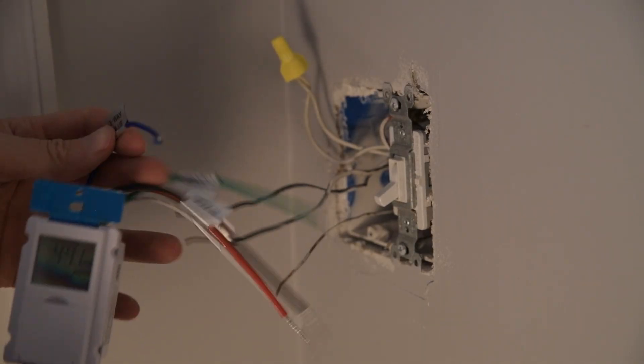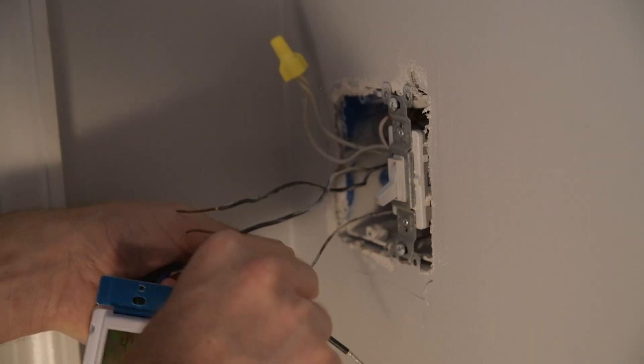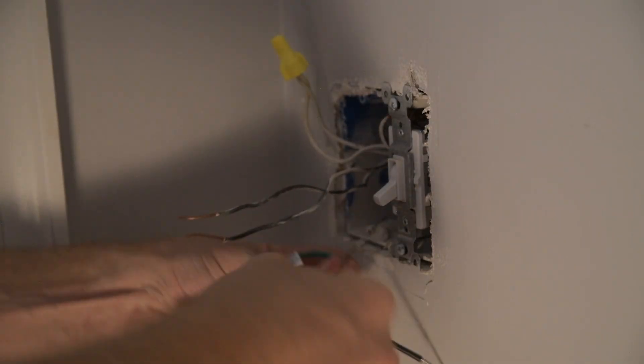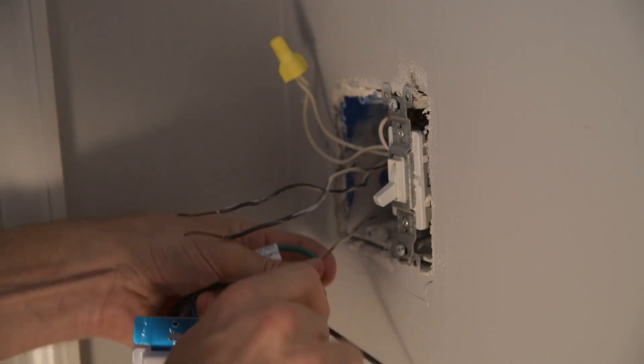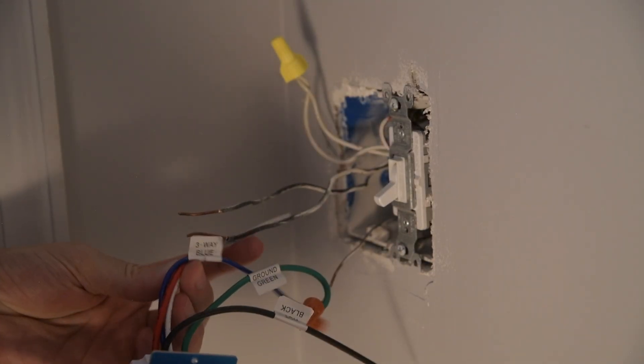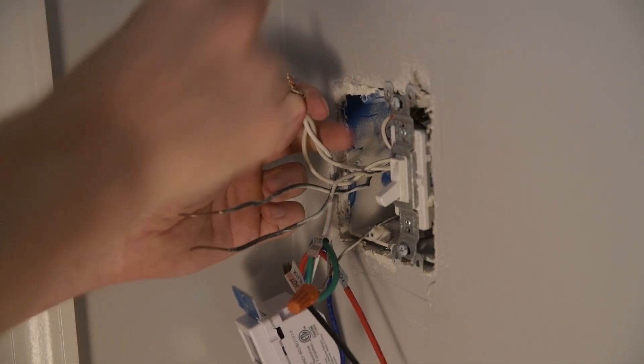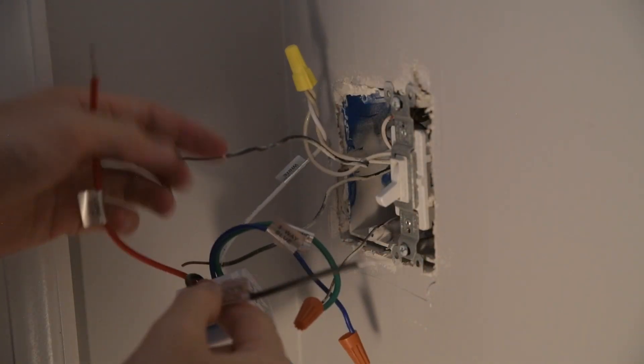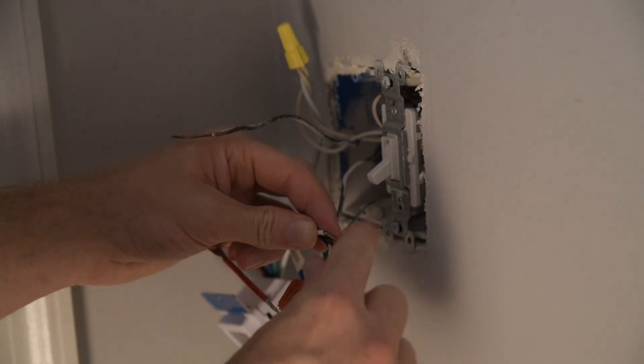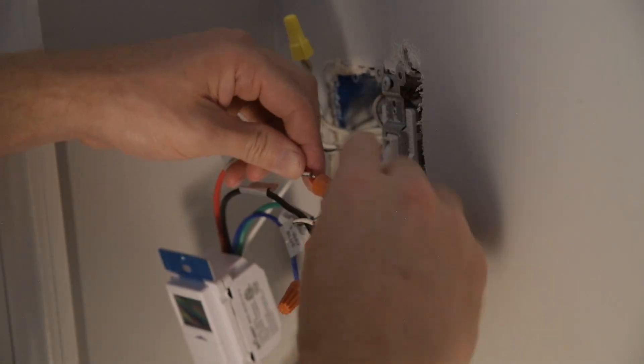Follow your specific wiring diagram for your switch. For ours, it comes with a blue wire for a three-way switch, so I'm putting a cap on that since this is not a three-way style. I always like to do the ground wire first — green is ground. Then white is the neutral connection, so I'll connect that to the bundle of white wires. For our model, the black wire is the line coming in, so line that up with the power source coming in. Then red is the power going out, the actual output of the device.